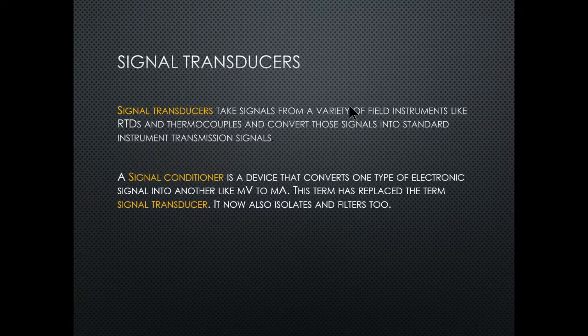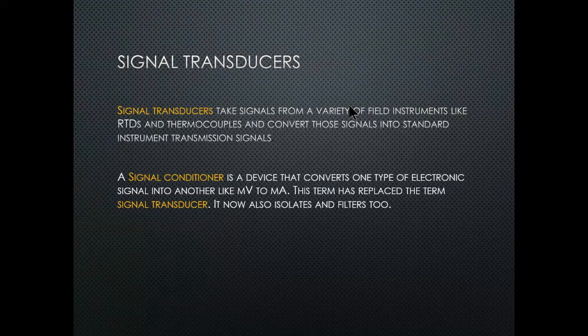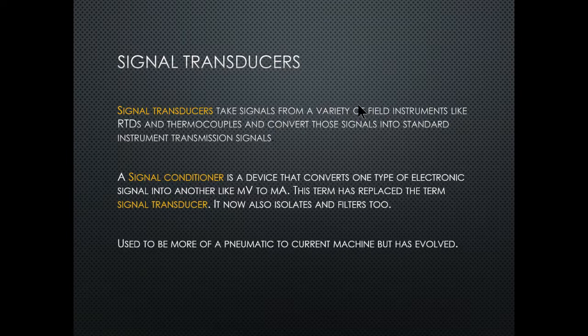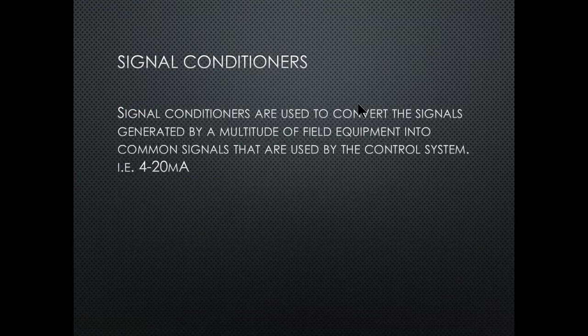A signal conditioner is a device that converts one type of electronic signal to another, like millivolts to milliamps. This term has been replaced by the term signal transducer. It now also isolates and filters signals. One of these things is actually an isolation device — it has galvanic isolation so there's no direct connection to the field such as wires and grounding. Signal conditioners are used to convert signals generated by a multitude of field equipment into a common signal used by the control system, like a four to 20 milliamp signal.